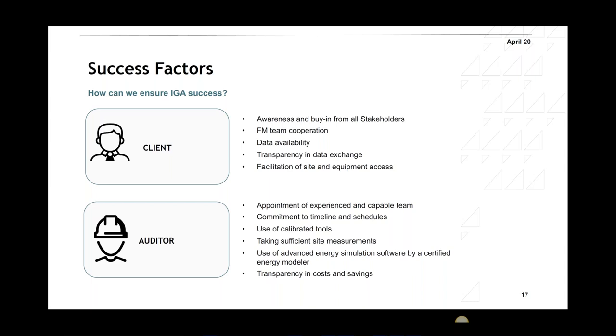The auditor: you should appoint an experienced and capable team. Let's say you are doing an audit for a hospital. You probably would want someone with maybe an HFDP or ASHRAE certification, or someone who has worked on hospitals before. We've worked on hospitals before, and it's not easy at all to do energy audits for hospitals. Commitment to timeline and schedules, use calibrated tools, take sufficient measurements, and use advanced energy modeling software by a certified energy modeler, preferably an ASHRAE BEMP. Also be transparent in the cost and savings. Don't just show that this energy conservation measure is going to cost you $3 million or dirhams, and not show why it's going to cost that much.